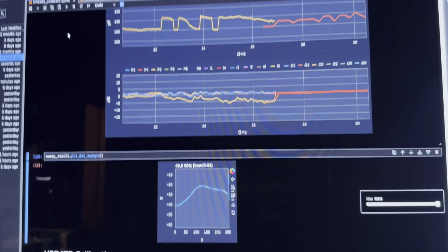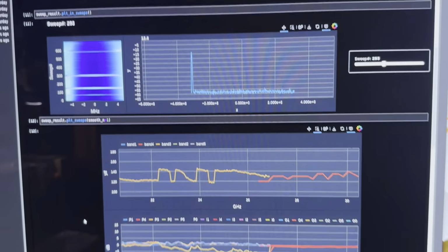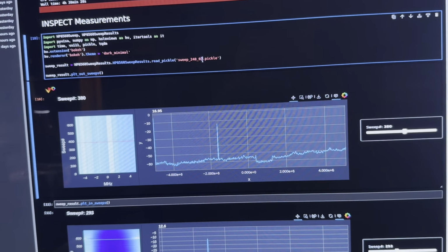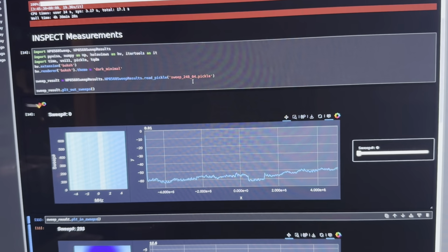So the calibration that you saw, the sweep that you saw, was actually the one that happened after I had made that change. So we don't have to wait another 5 hours, because the 5 hours that we waited were the 5 hours after that change. And so we can see we've got a new sweep, can't really see much in there. But where we do expect to see a change is here. We don't want to see that divot anymore.